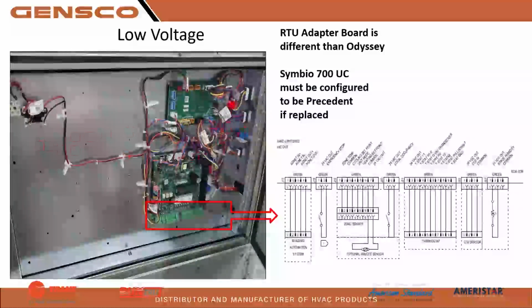So when we open this up, we'll be able to see the back side of this. And then here is our thermostat connection. I got another picture of that, but if you're using a standard 24 volt, everybody, that T-stat ground is your common. And then you have your BAS, building automation system, is going to communicate right here.